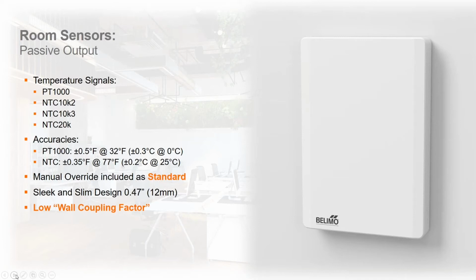One big feature we're pushing for all of our passive sensors, including the setpoints, is a manual override button included as standard. As an application example, if you have a BMS system with certain zones or rooms that are unoccupied and on standby or on a timer, an office member coming in early before working hours, or a cleaning agent coming in after hours, can walk into the room and hit the manual override button. The override shorts out the thermistor and sends a signal to the BMS system to wake the room up and condition it based on its programming.